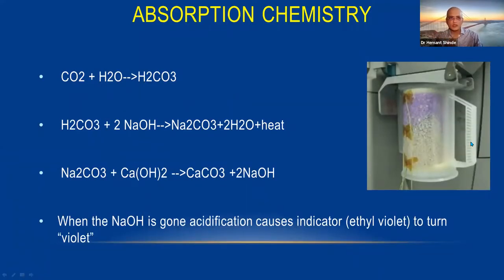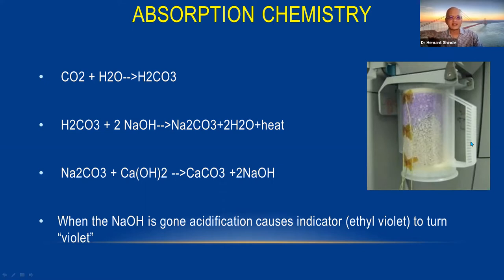Soda lime absorption chemistry is the most important part of our low flow technique. CO2 exhaled by patients reacts with water to form H2CO3 (carbonic acid), which reacts with sodium hydroxide to produce sodium carbonate, heat, and water — an exothermic reaction providing humidification and warmth. This then reacts with calcium hydroxide to give calcium carbonate and sodium hydroxide, changing the indicator color to violet.